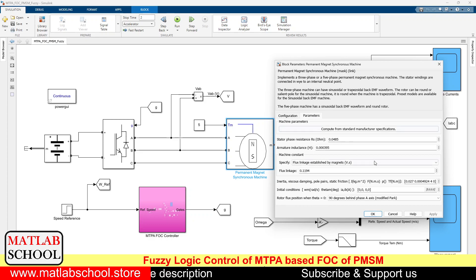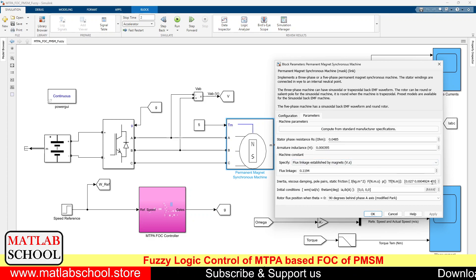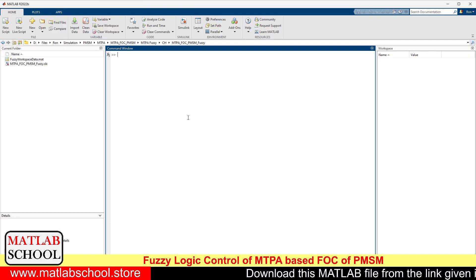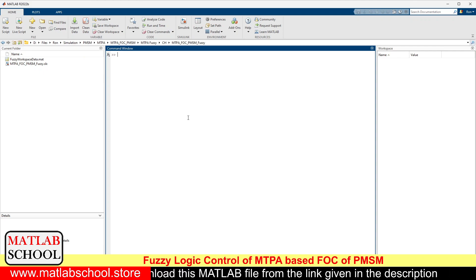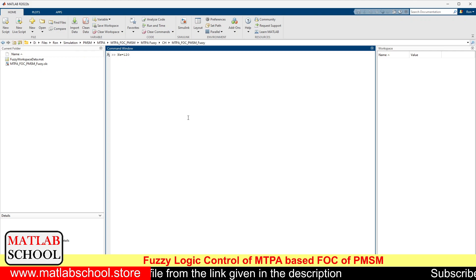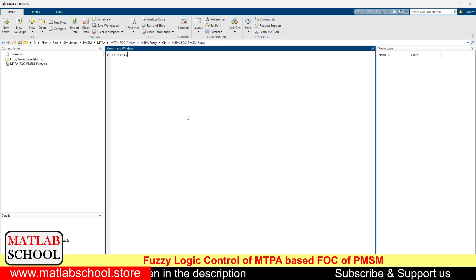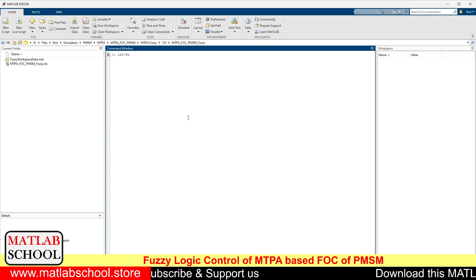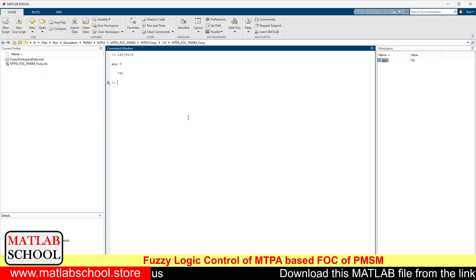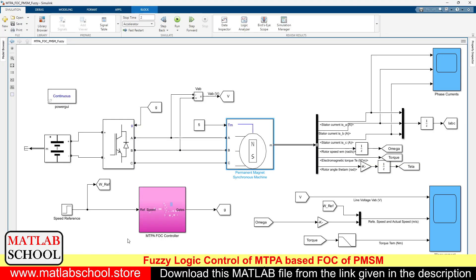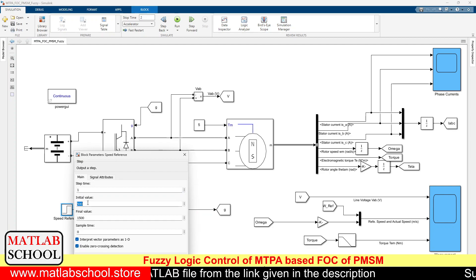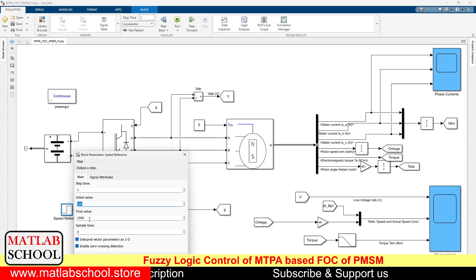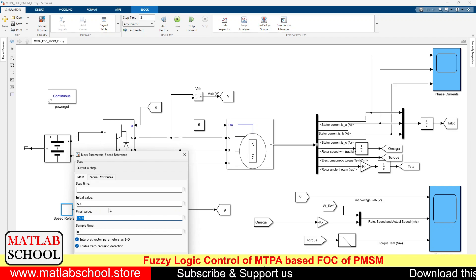Let us calculate the synchronous speed of the motor. Its number of poles will be 8 because the pole pairs is 4. We shall calculate the reference synchronous speed using the formula: Ns = 120F / P. With frequency of 50 Hz and number of poles equal to 8, the synchronous speed is 750 RPM. The initial speed reference is 500, and after one second it will be 1500 RPM.